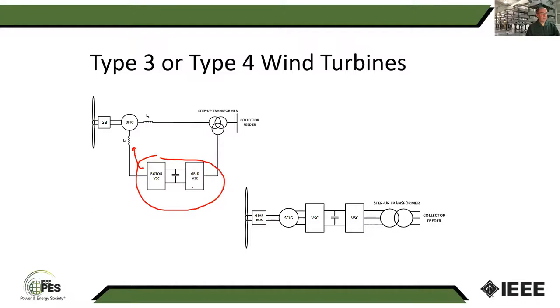And the way this converter is controlled is it measures the DC voltage. So if the power that's going through this converter is less than the power going this way, that DC voltage falls because you start pulling energy out of the capacitor. If the imbalance is in the other direction, so there's more power coming this way than is going out this way, this voltage rises. And so by putting a closed loop voltage control on this, you can control the power that this consumes or supplies to the power system. And so that's one of your degrees of freedom. And so a lot of schemes like this are set up where you control this voltage based on a slave. So this is the master, this is the slave.